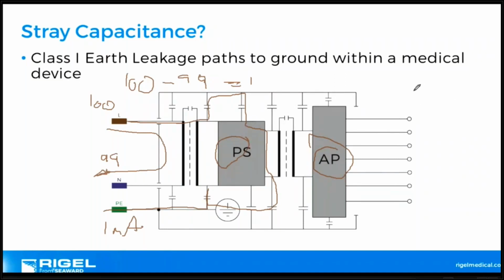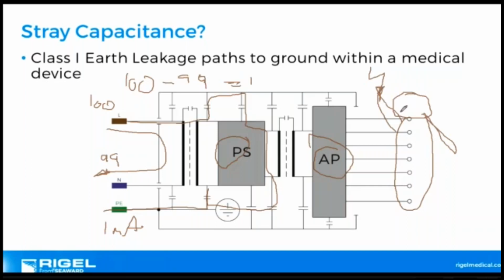If I have the scenario where I've got a patient, these are the applied parts, right? He's on a hospital bed, or she, and they're unfortunate enough to touch a hazardous current source or voltage source. We need to make sure we have an isolation barrier there, because if they touch this electrical source, the current will flow through the device and back down to earth, and this person is going to get an electric shock. So what the medical equipment manufacturer needs to provide, especially for BF and CF type equipment, is this isolation barrier. So this is floating. This has no connection to protective earth. Just something to bear in mind.